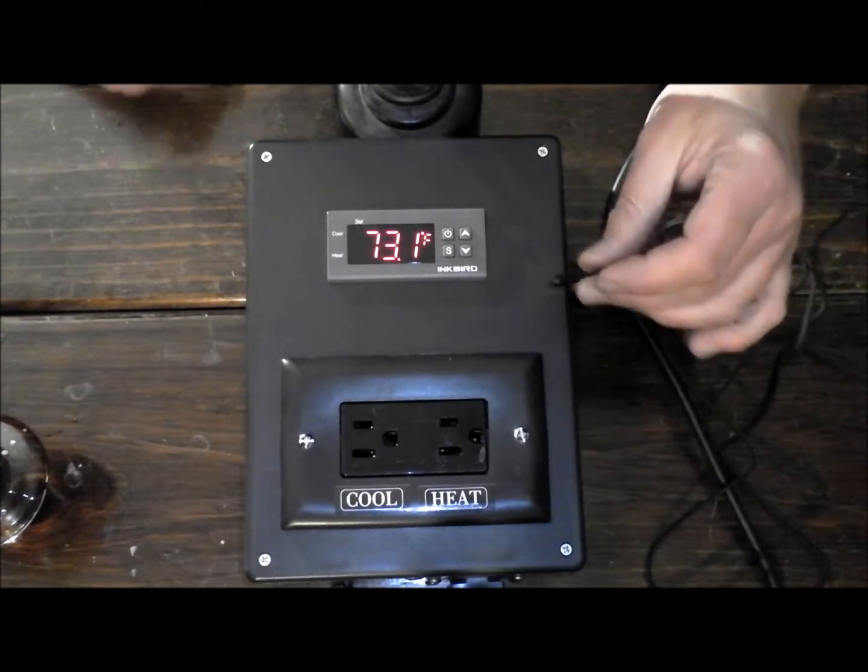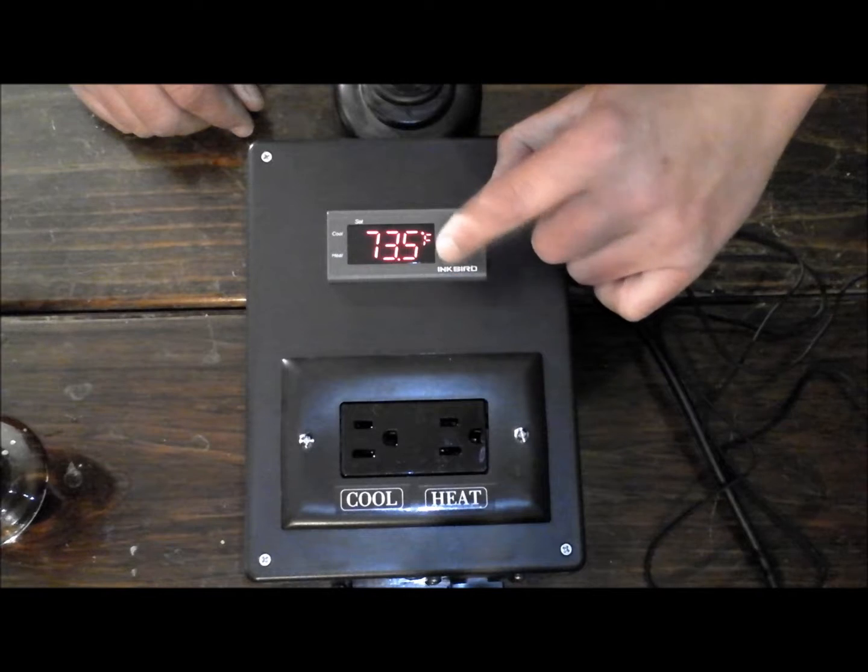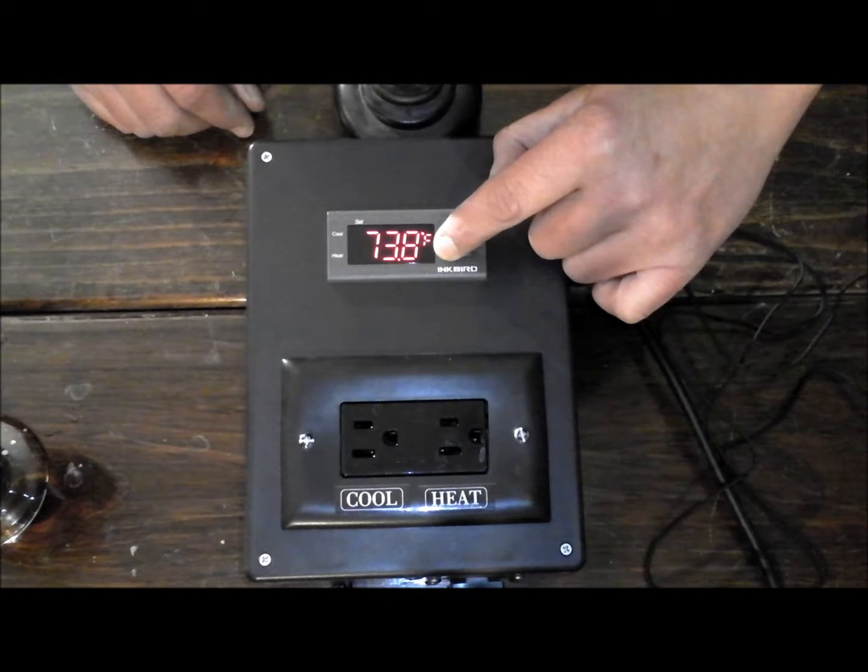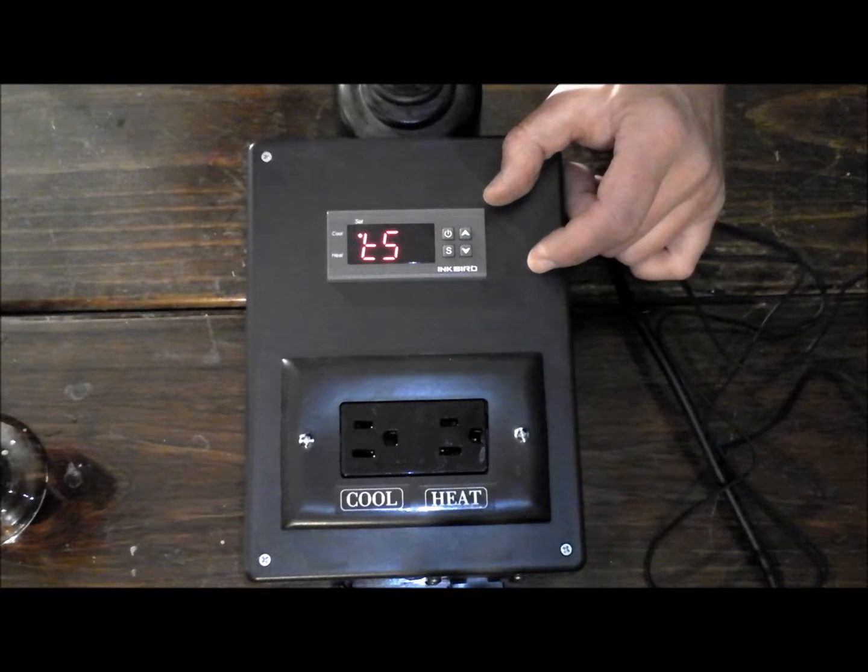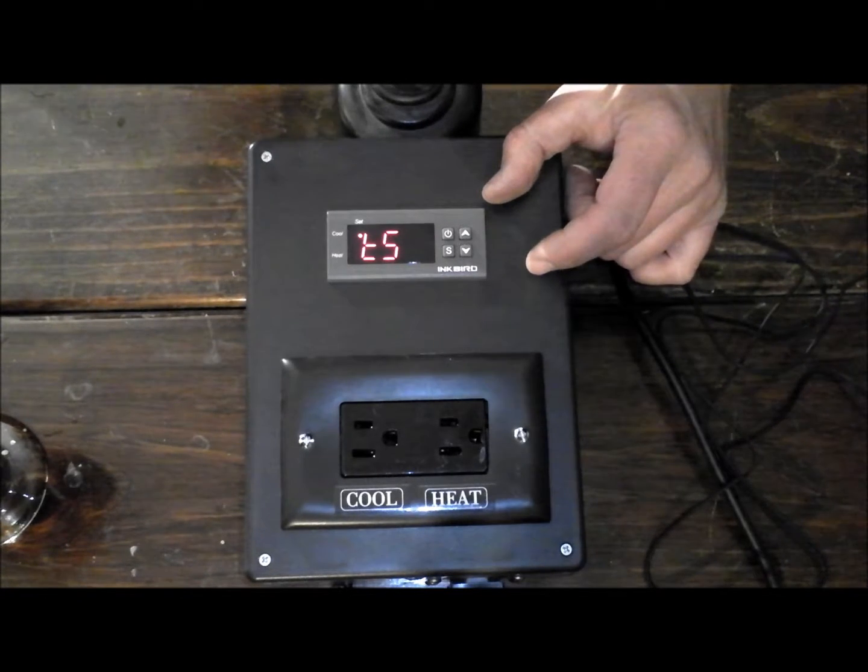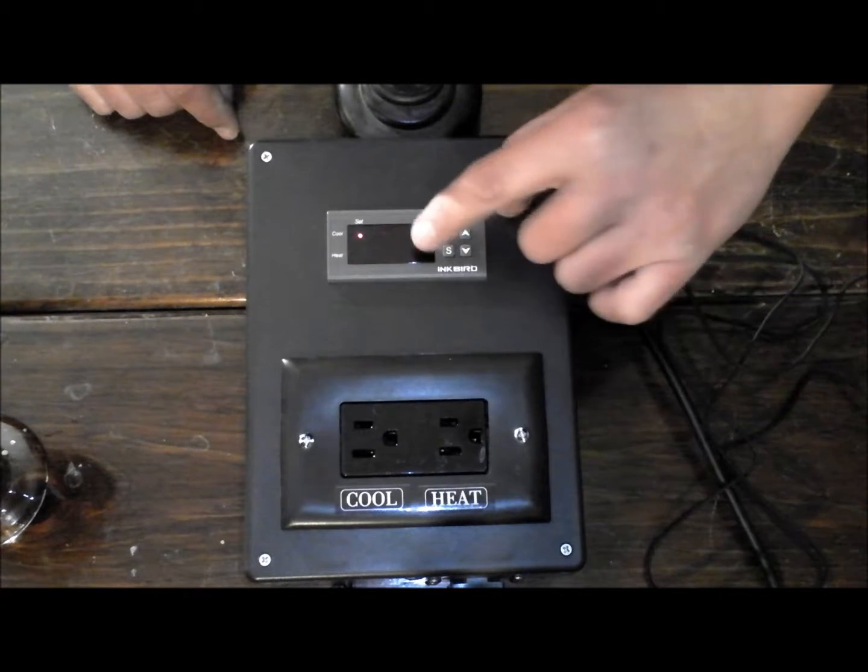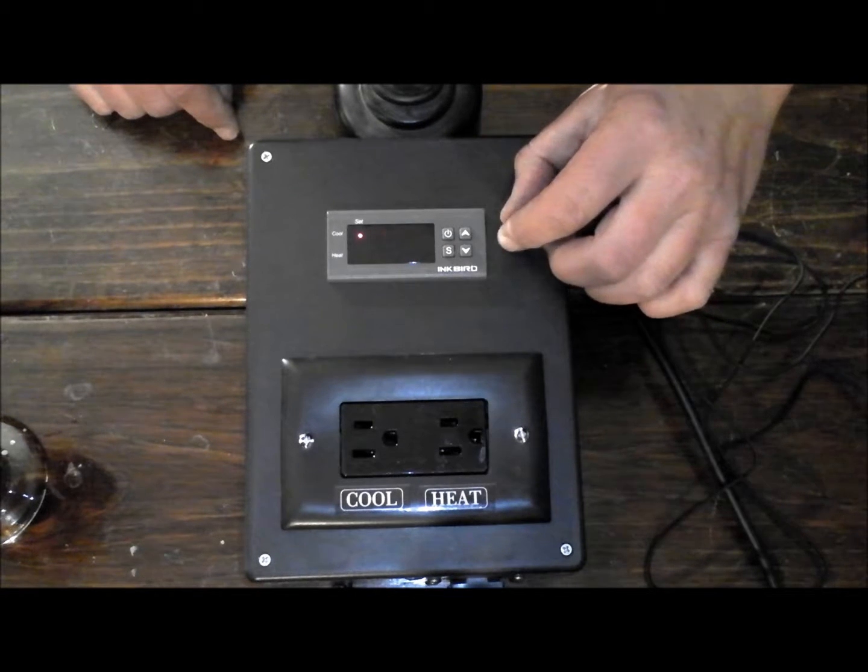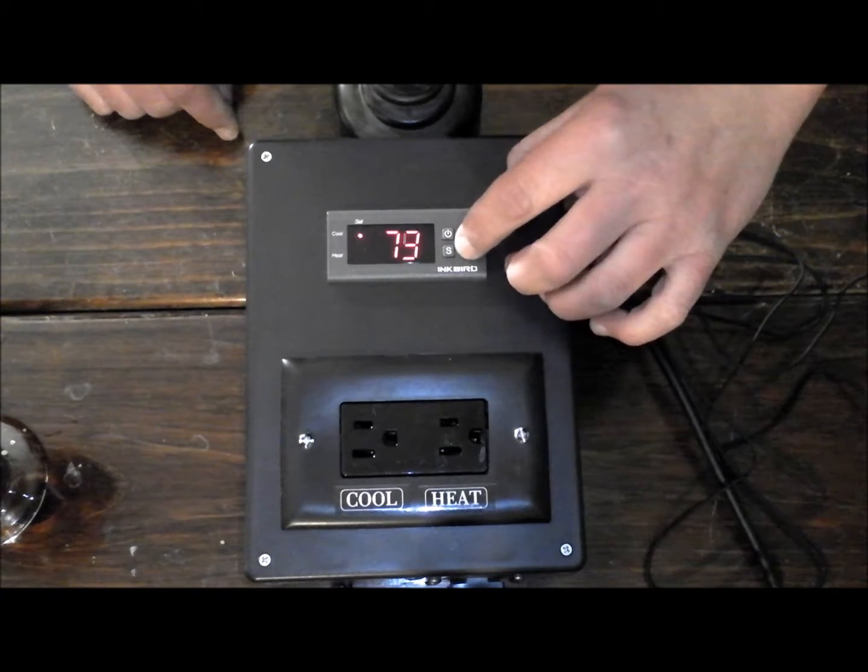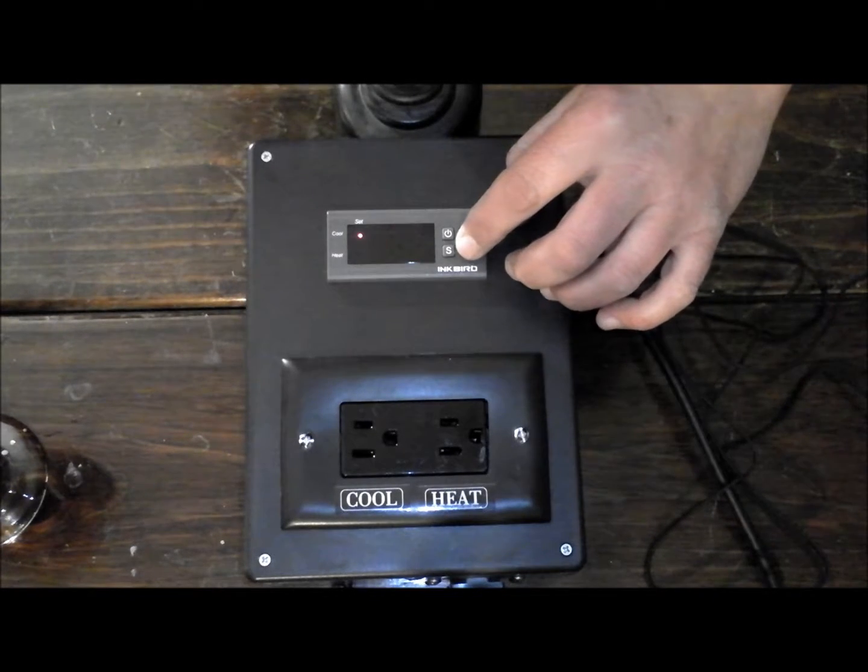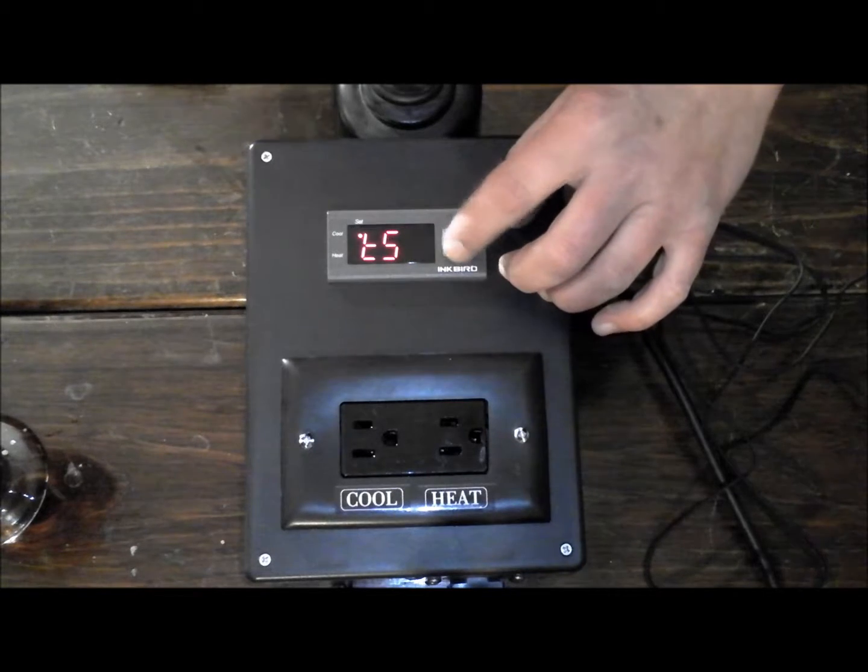Now as far as how it works, you have your S button here, which you hold down for 3 seconds, and that goes into your set mode. The TS is your temperature set value, which is what you want to maintain the temperature at. You hit it one more time, right now it's set for 73 degrees. You can turn it up or down. The range goes from minus 50 to 210 degrees, so we have plenty of range.